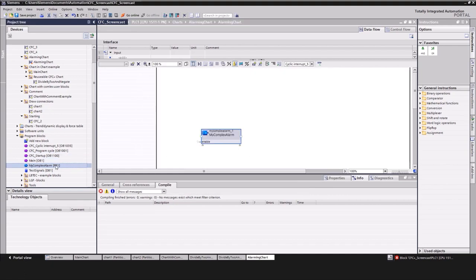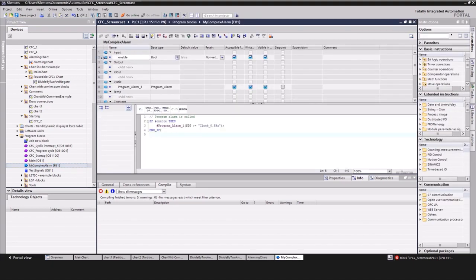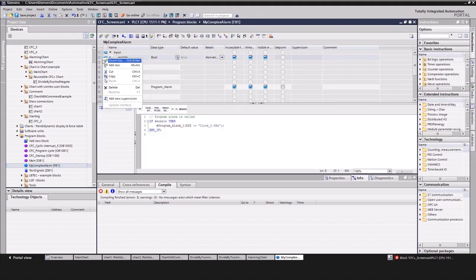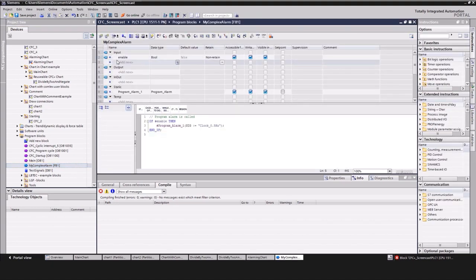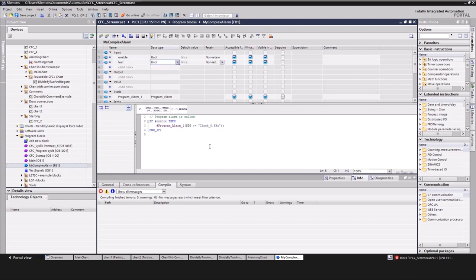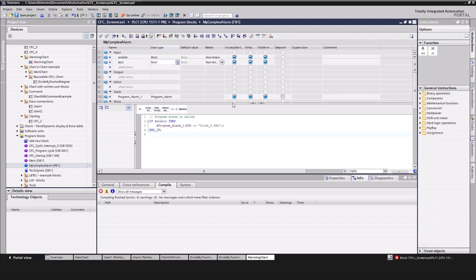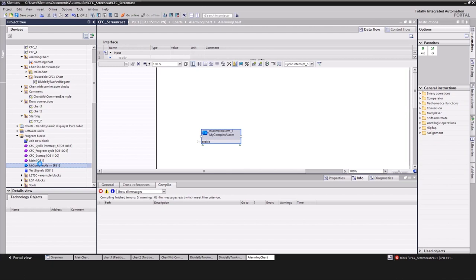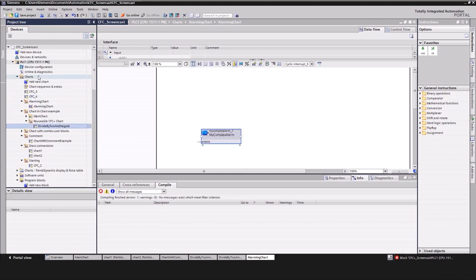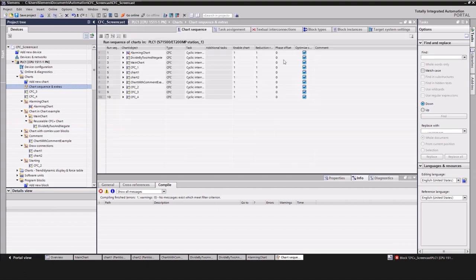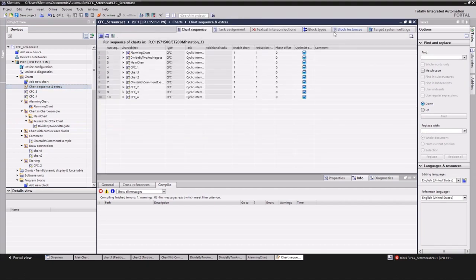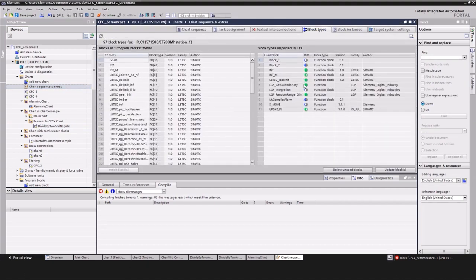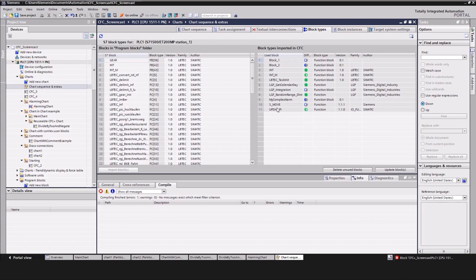Of course, after improving the logic of the block, an update is possible. For this, we add an extra input and compile it. To conclude, go to the chart sequence and extras and navigate to the block types. There, you have the option to execute an update. As a result, the new input is added.